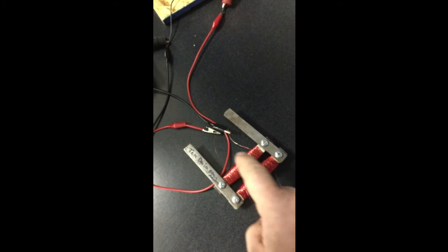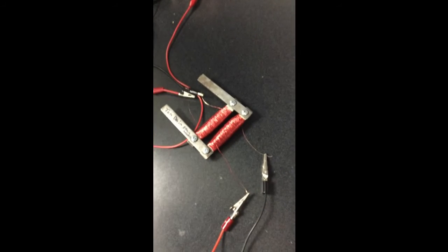I'm going to just show the meter reading here. So we got 15 volts coming out of the transformer, and you're only showing 1.58 here. So it's about 10%. And that could be anything, could be how it's wired, but you can see this is a lot heavier than what this is here. So you got a big voltage drop.